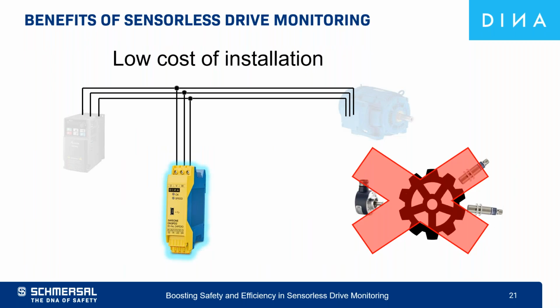Due to not requiring sensors or encoders, the only thing that needs to be installed is a few wires and the standstill or safe speed monitor in the panel. This is less intrusive on the machine, as well as less likely to be manipulated or damaged in the field.